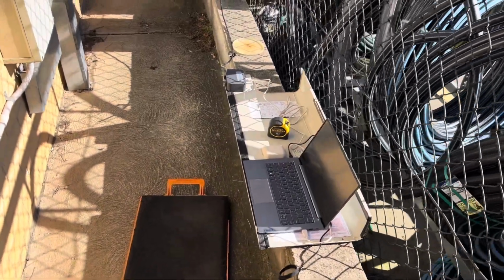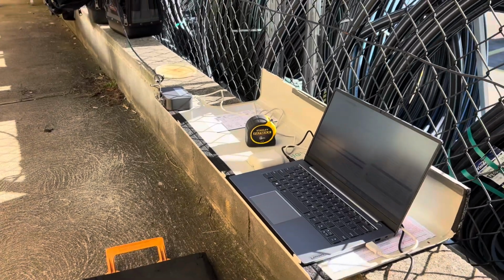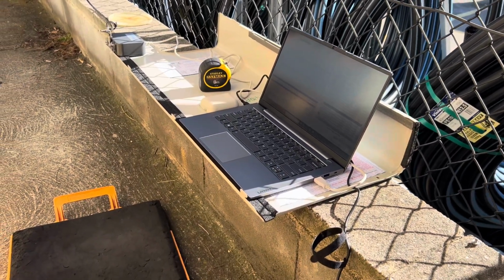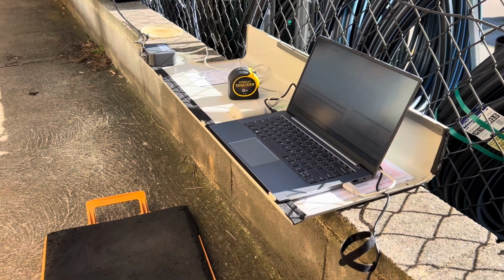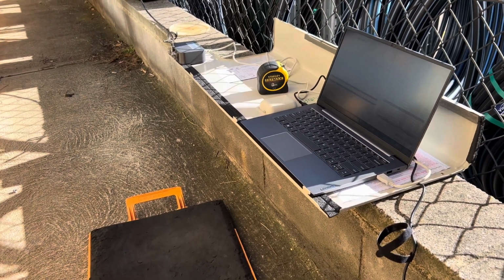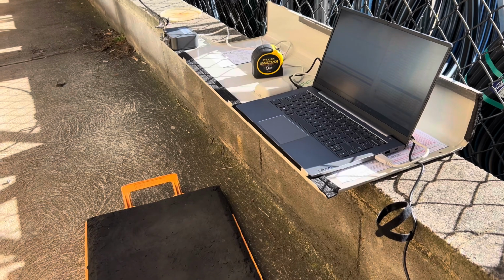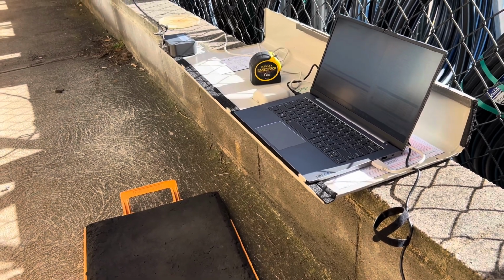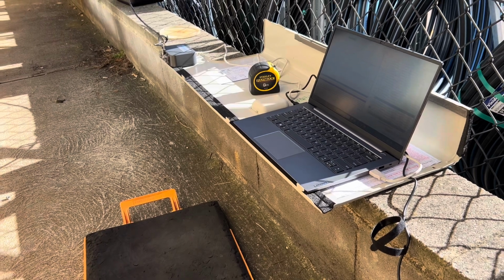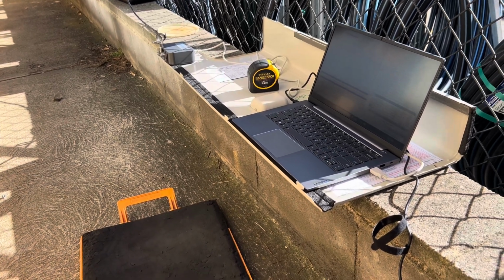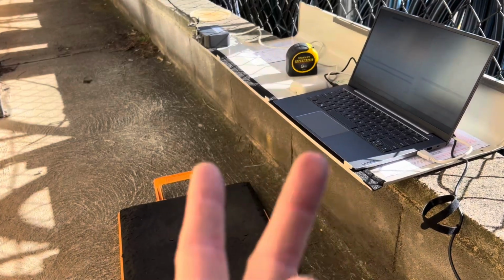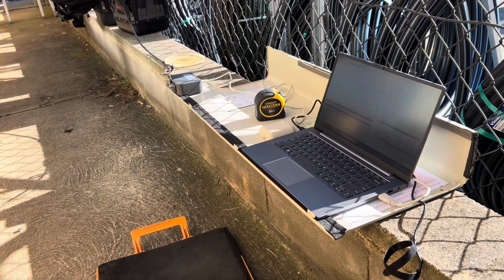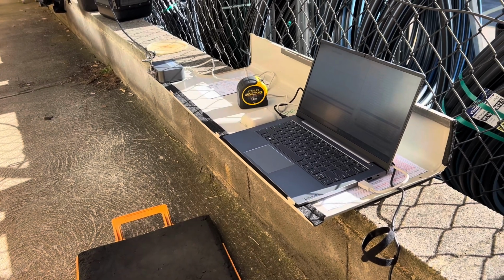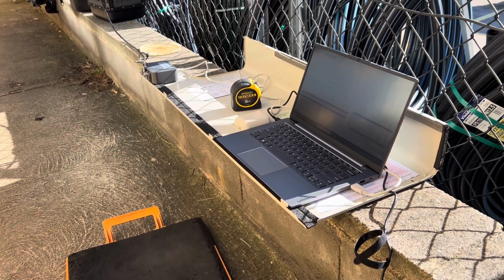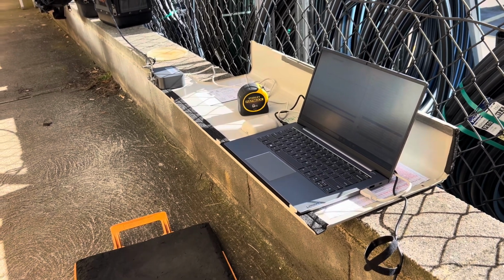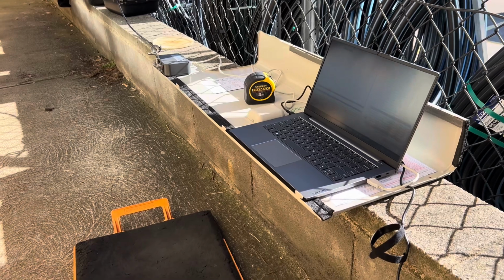Okay, so another issue outside of using a heat pump instead of a heat recovery. So the office space and the lunchroom, the lunchroom is slightly bigger, right? And it's also a high use area. So the 2 unit sizes, I've got a 3.2 and a 5, right? The 5 is in the office and the 3.2 is in the lunchroom. I'm gonna hazard a guess, it probably should have been flipped, and the 5 kilowatt was supposed to go into the lunchroom and the 3.2 was supposed to go into the office, which also would explain why we're overheating in the office space enough that it kicks back into cooling mode.